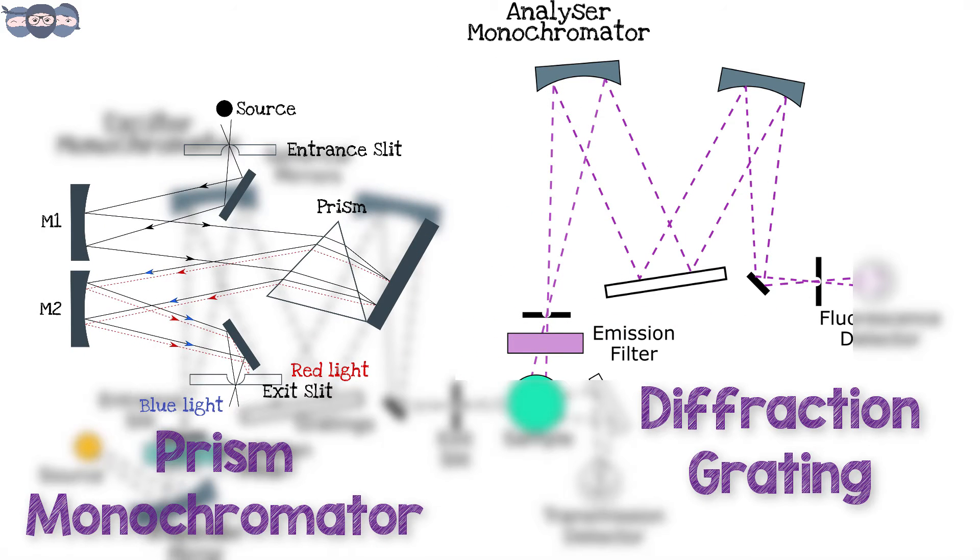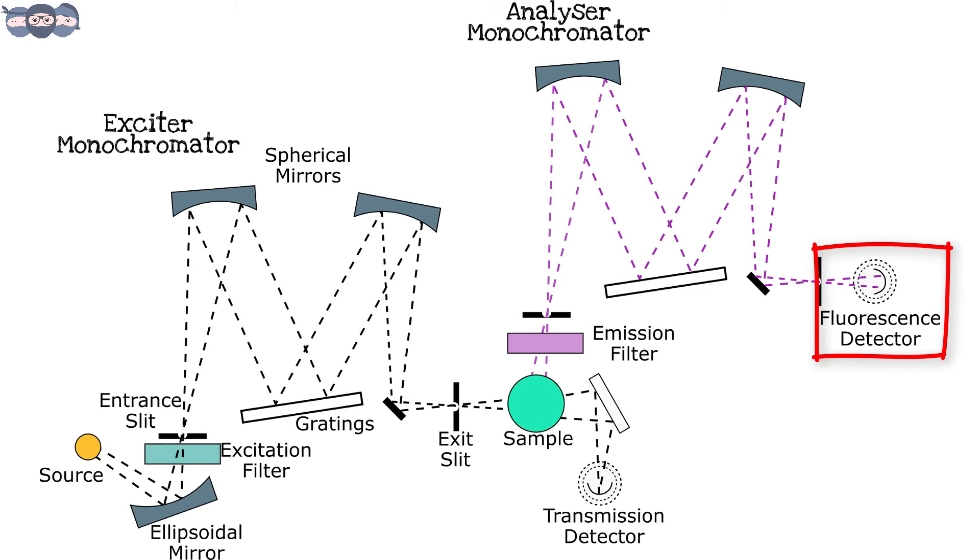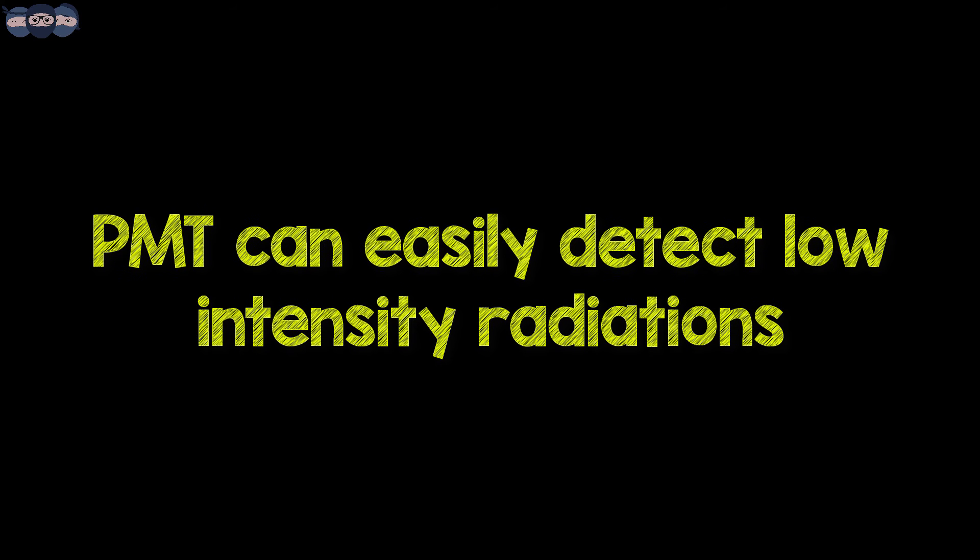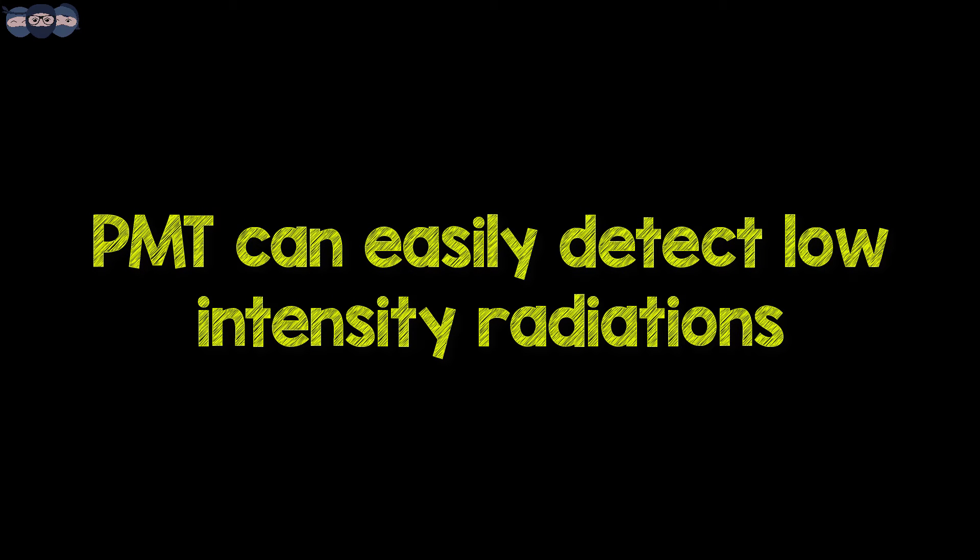The analyzer monochromator is also a prism monochromator or a diffraction grating. The next component is the fluorescence detector, which is generally a PMT. PMTs are used as even the slightest radiation or low intensity radiation is easily measured by them.